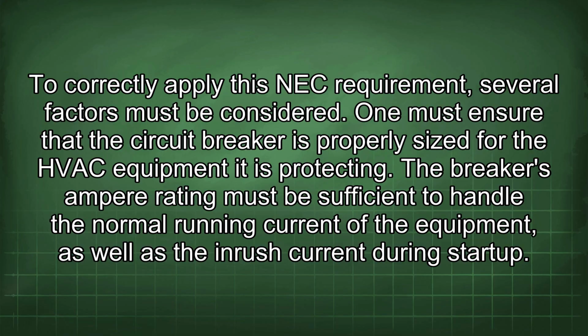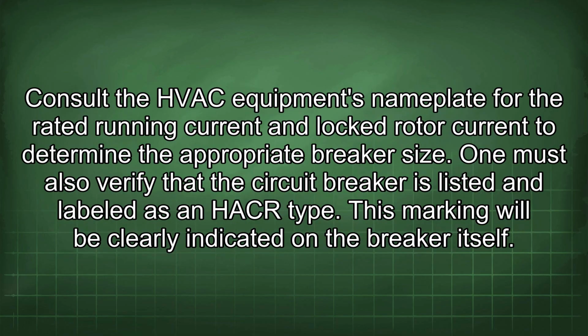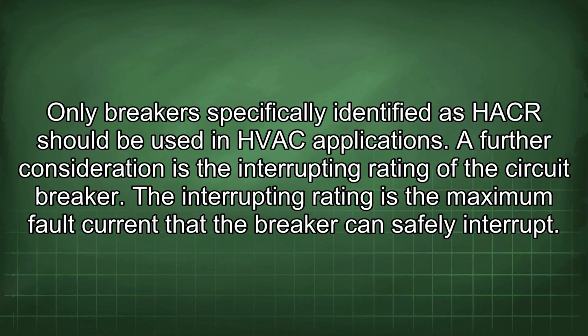To correctly apply this NEC requirement, several factors must be considered. One must ensure that the circuit breaker is properly sized for the HVAC equipment it is protecting. The breaker's ampere rating must be sufficient to handle the normal running current of the equipment, as well as the inrush current during startup. Consult the HVAC equipment's nameplate for the rated running current and locked rotor current to determine the appropriate breaker size. One must also verify that the circuit breaker is listed and labeled as an HACR type. This marking will be clearly indicated on the breaker itself. Only breakers specifically identified as HACR should be used in HVAC applications.